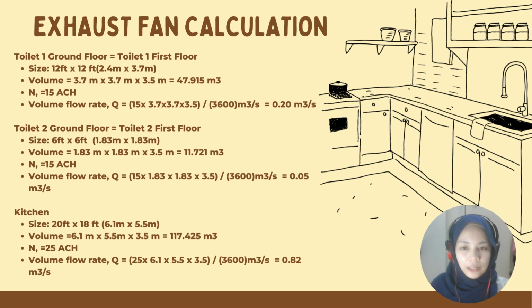And lastly is the kitchen. Our kitchen size is 20 feet times 18 feet. Volume is 117.425 meters cubed and is 25 ACH. Our volume flow rate Q is 0.82 meters cubed per second.